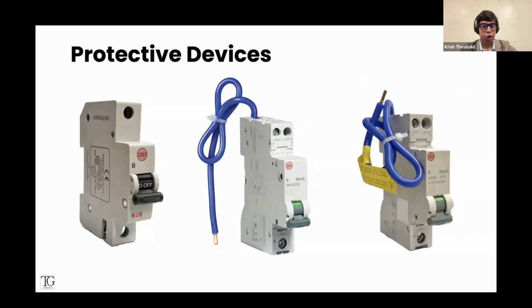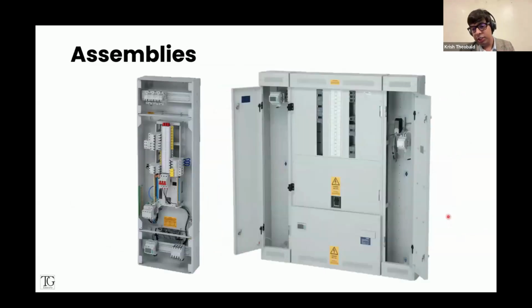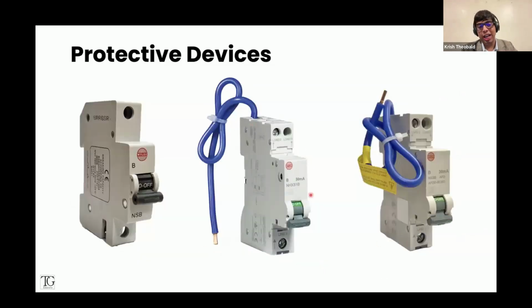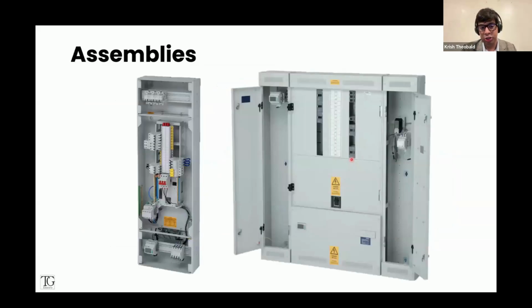So this is just, yeah, we've got your MCB here, your RCBO here, and then your RCBO AFDD as well, which is now required in certain locations like domestic dwellings. Assemblies, this is an important one. We tend to select protective devices rather than assemblies, but remember the product that we use in the installation is an assembly. So we have the 61439 series of standards. Now, if it's to be operated by ordinary persons, the assembly, which is the protective device, bus bar, everything together, has to comply with 61439-3.